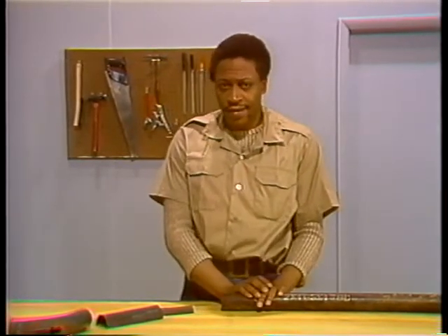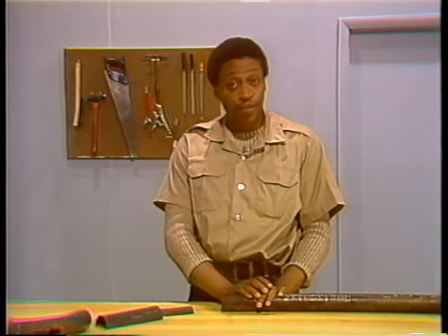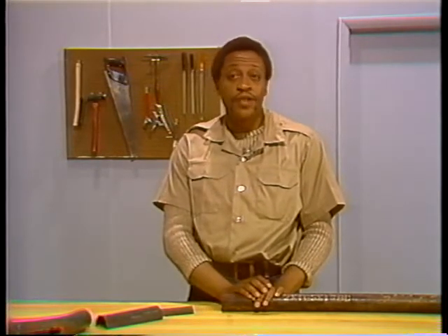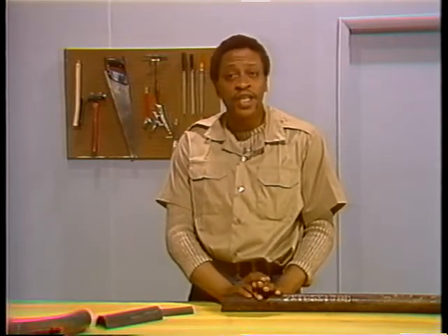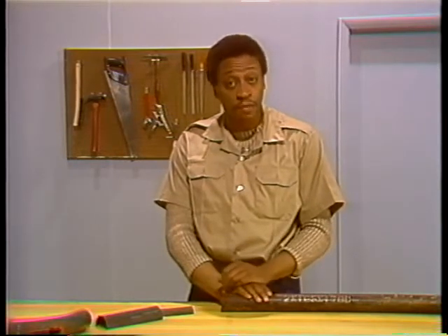Boiler tubes are constantly exposed to intense heat. In fact, the temperature is so high that it could melt the tubes. The reason they don't melt is that the water and steam flowing through them keep them cool. Although that water and steam are very hot, they are still cool enough to keep the tubes from melting. Overheating and possibly tube failure result when water or steam are prevented from cooling a tube.